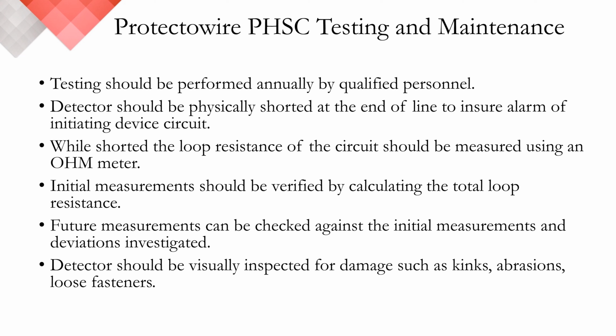When measuring the loop resistance, place each circuit in alarm and leave the short across the detection as described above. Disconnect each detection circuit's wires from the terminals of the control panel. Place an ohm meter across the disconnected zone wires, out positive and out negative, and record the resistance measured. Compare these values at each annual testing. Any change in loop resistance should be investigated for possible deterioration of the inner conductors, with particular attention given to termination points, inline splices, or areas of the detector where the outer jacket has been compromised or damaged.